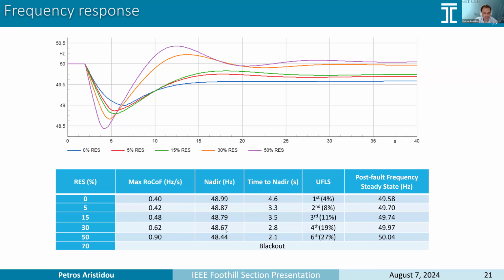Currently, in most cases, the Cyprus system is not secure if we don't have under-frequency load shedding. In most cases, during the summer and during spring, especially where we have low loading conditions and high renewables, the under-frequency load shedding is the only reason why the system can maintain security. And this is something that we want to fix, because it happens frequently that it gets tripped and lots of consumers get disconnected, reliability falls, etc.